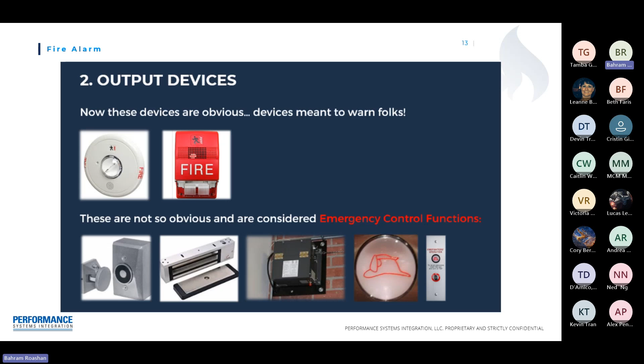Output devices. An output device is a piece of hardware that converts data from the fire alarm control panel into a form that humans can perceive. Output devices receive a signal from the fire alarm control panel, changing a status, such as causing a horn strobe to go off. There are other devices that are not so obvious, such as lock releases to open or shut doors, and elevator recall to shut down the elevator system and return it to the main floor. HVAC systems can receive a signal from the fire alarm control panel to shut down the HVAC system. This prevents the spread of smoke and fire throughout a building by stopping the airflow.